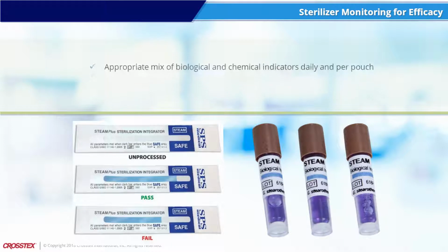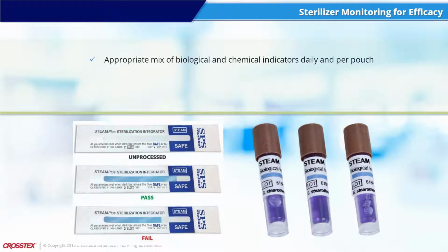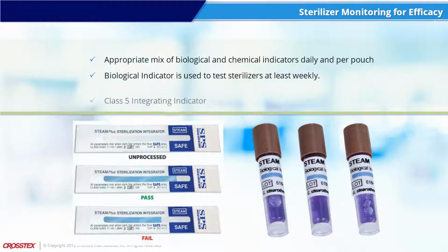Sterilizers should be monitored for efficacy with the appropriate mix of biological and chemical indicators on a daily and per pouch basis. Biological indicator is used to test sterilizers at least weekly. Class 5 integrating indicator is used to monitor every load. Steam chemical indicator is used to monitor every pack.